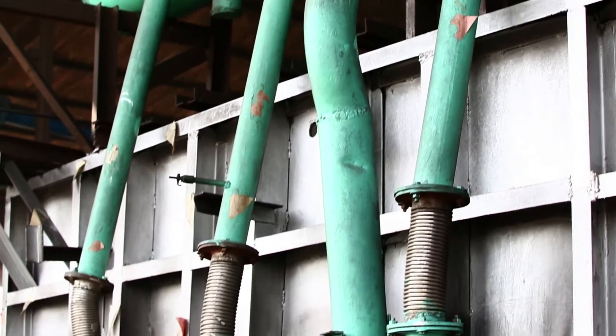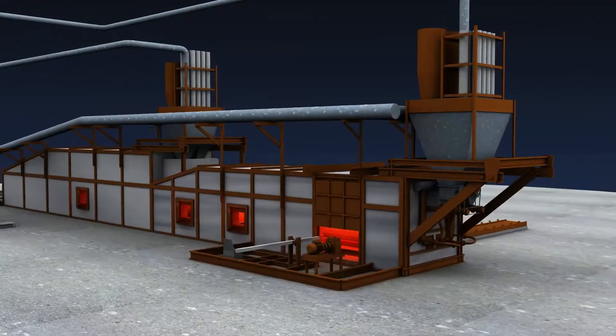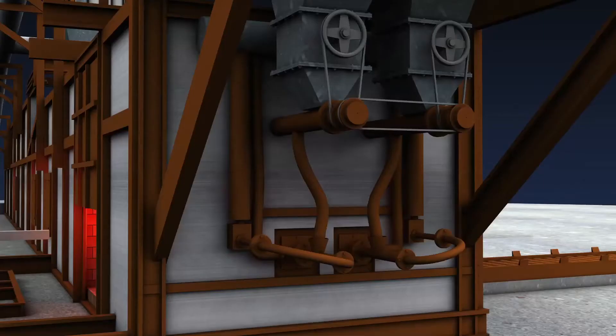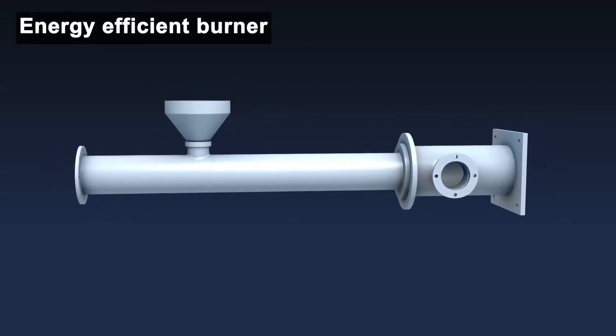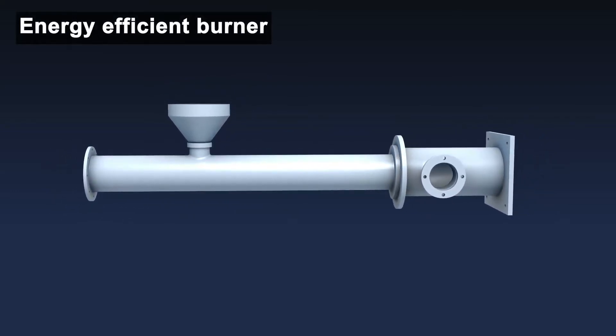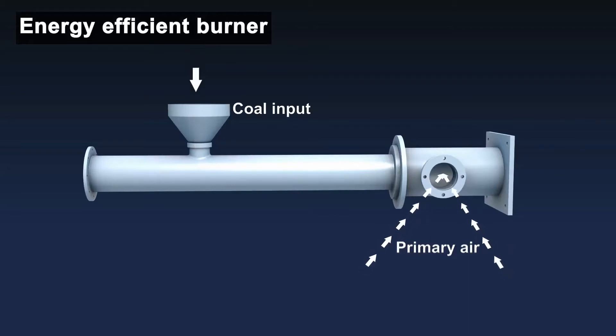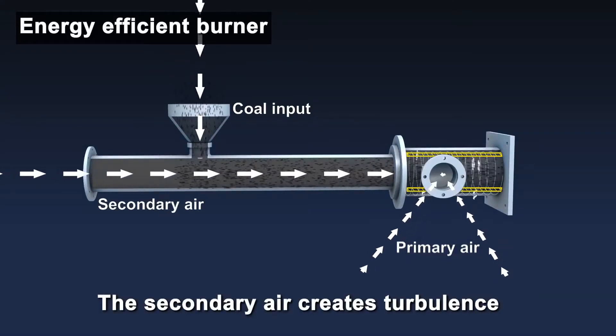In a swirl burner, secondary air is supplied along with the primary air in an annular arrangement. Both primary air and secondary air are hot airs drawn from the recuperator. The swirl burner typically has three inputs. The closest input towards the furnace is for primary air, which is directly fed from the recuperator. Coal is fed from the next input in a controlled manner from the screw feeder attached to the overhead hopper. The third input is for the secondary air which pushes the coal into the burner.